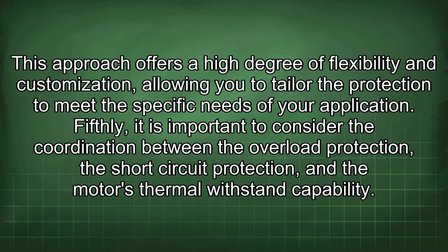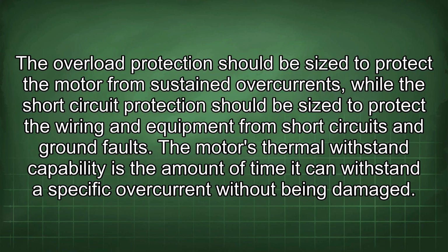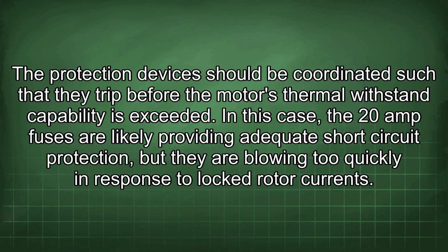Fifthly, it is important to consider the coordination between the overload protection, the short-circuit protection, and the motor's thermal withstand capability. The overload protection should be sized to protect the motor from sustained overcurrents, while the short-circuit protection should be sized to protect the wiring and equipment from short circuits and ground faults. The motor's thermal withstand capability is the amount of time it can withstand a specific overcurrent without being damaged. The protection devices should be coordinated such that they trip before the motor's thermal withstand capability is exceeded.